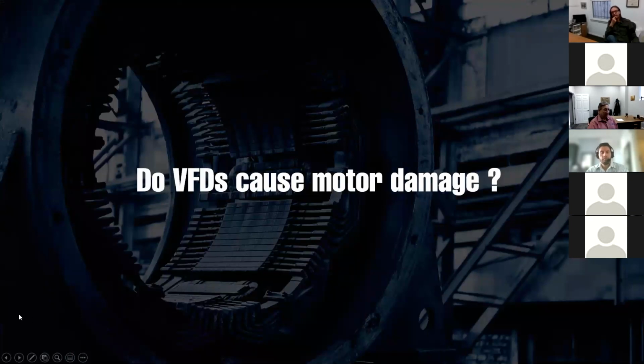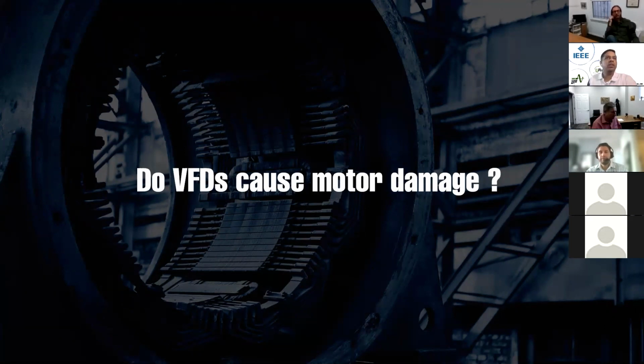So my first question: did we get any comments on experiences of VFDs believed to have caused damage to motors or machines? Yeah, we did actually, from Mr. Matsuda. He said he has seen 6-pulse VFDs cause damage to motor shafts with fluting and also damage to first phase winding turns from reflected waves. Great. Those are topics we can address today, so I'll make sure we've included that here. Any others? That's the only thing, but I would like to know what fluting means. I had never heard the term before. Well, just hold on. I've got a slide labeled fluting, so I think we can address that one.